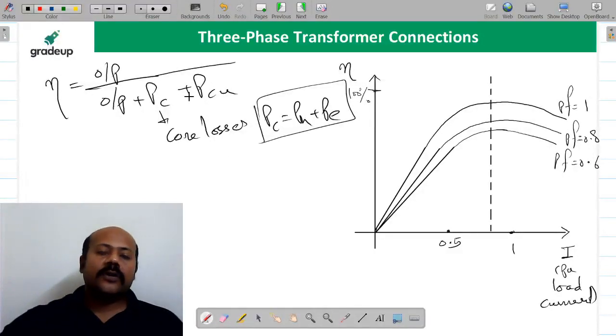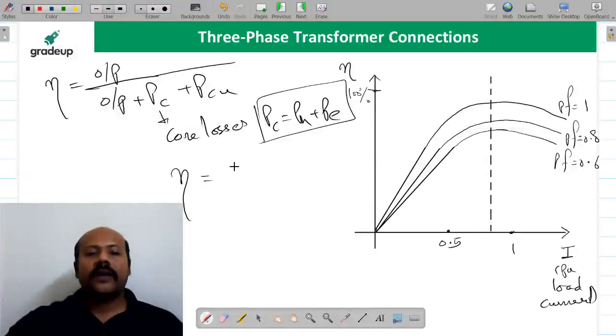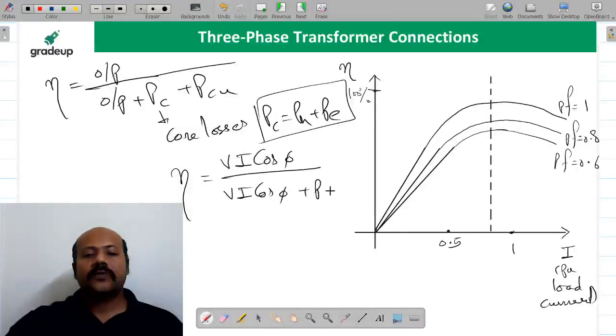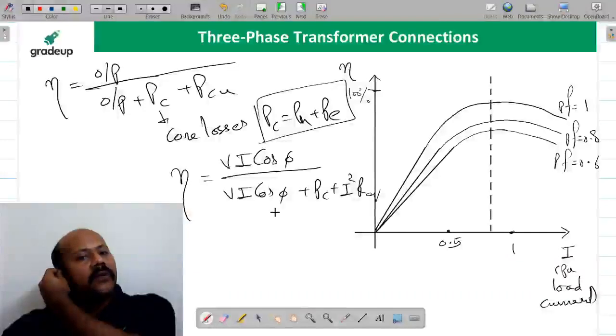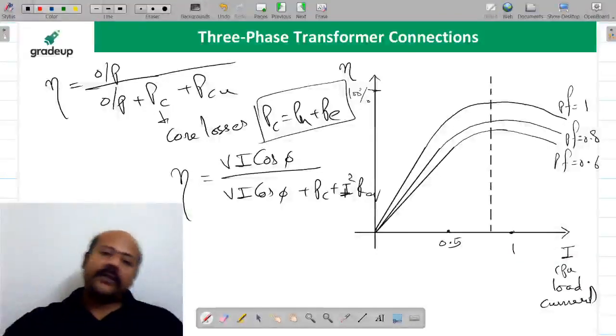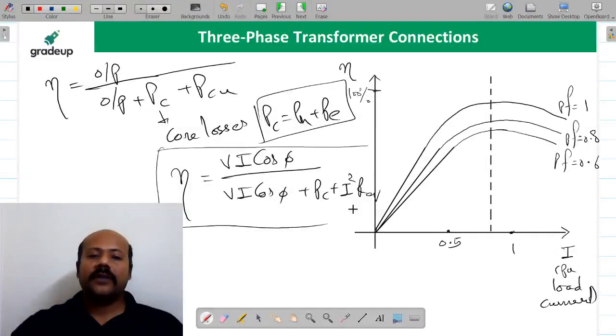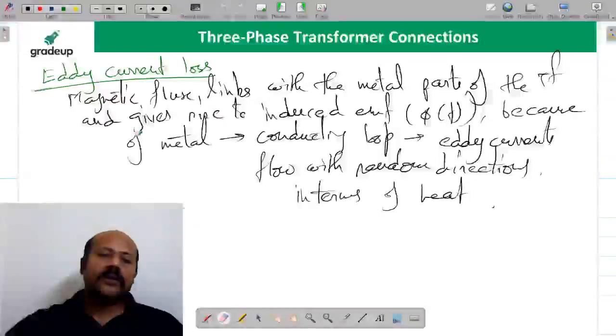Now, suppose we are talking about efficiency at full load condition. For the full load condition, if you want to find the efficiency, it is Vi cos phi, which is the output, upon Vi cos phi plus Pc plus I square R equivalent. Now there are two cases if you want to see the maximum efficiency case. In general, this is the equation for efficiency. Now if you want to see the maximum efficiency condition, let me remove this so that we can discuss the maximum efficiency condition.